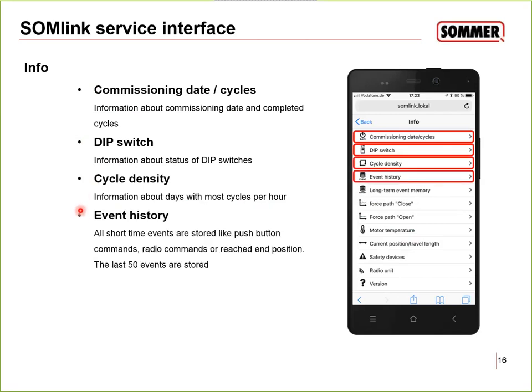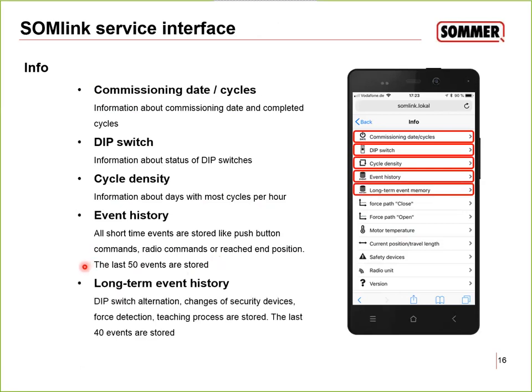Event history. So here you could read out the last 50 events. They are stored. So all the commands, like radio commands, you can read out. Operator, for example, was started by push button 1 from the transmitter, and it's overwriting, so you always got the newest events over here. The old events will be overwritten. There is a long-term event history as well available. So here, for example, if somebody changed the dip switches, it will be logged on here, so you can see this over here. The last 40 events are stored at this position over here.